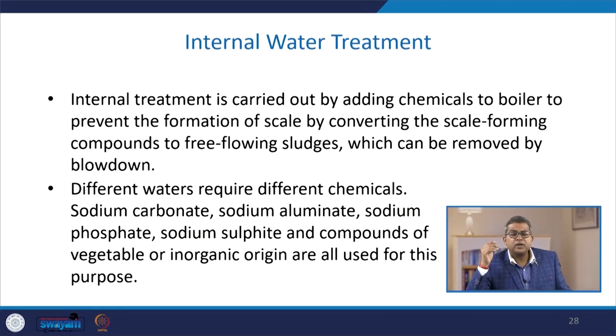Internal water treatment is carried out by adding certain chemicals to the boiler to prevent scale formation by converting scale-forming compounds into free-flowing sludges, which can be removed by blow down. Different waters require different chemicals; sodium carbonate, sodium aluminate, sodium phosphate, sodium sulphite, and compounds of vegetable and inorganic origins are all used for this purpose.